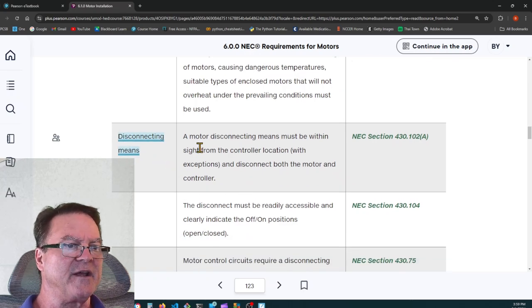Disconnecting means, I've got this highlighted. Motor disconnecting means must be within sight from the controller location and disconnect both the motor and the controller. That's 430.102(A).